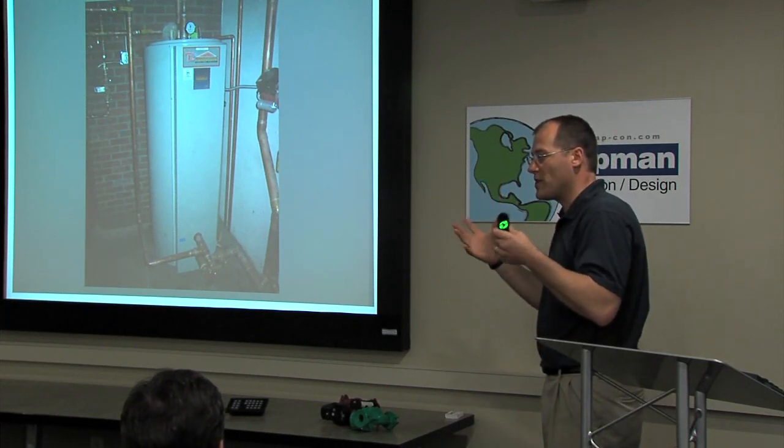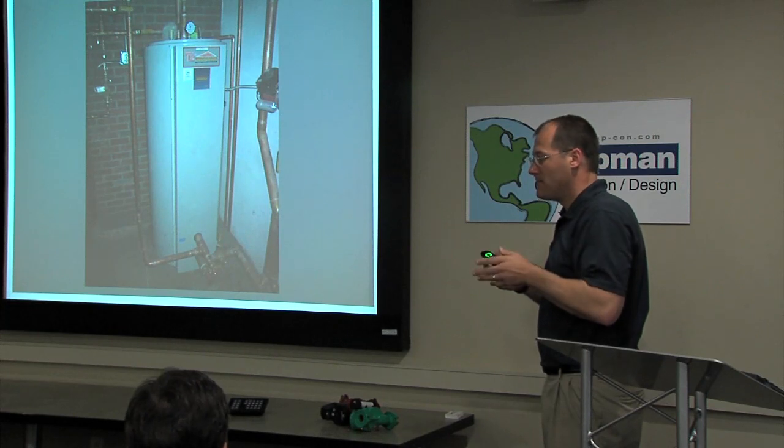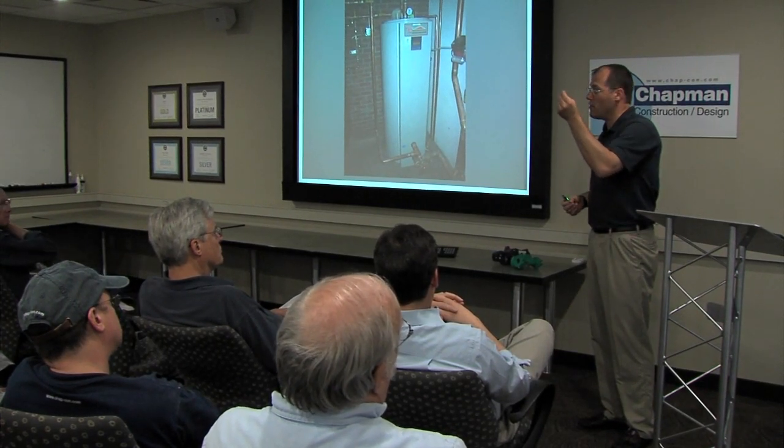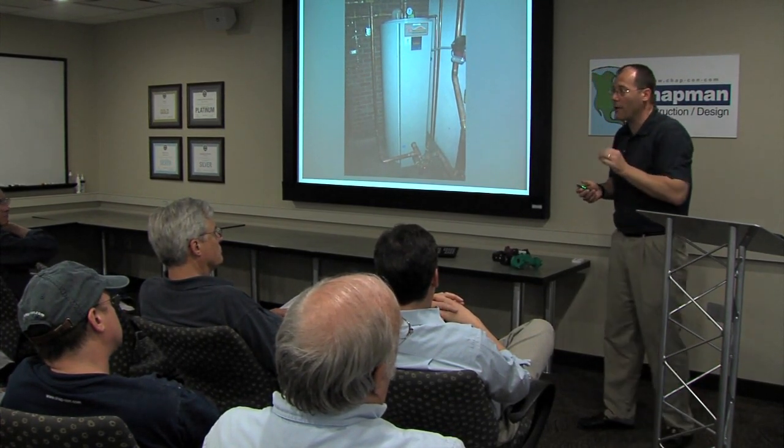As rules of thumb, we always think about 220,000 BTUs as about the most horsepower I can put into a 120 gallon tank of water. I just can't pump any more through that, and the surface area is not big. Flip that around and you can get about 900,000 BTUs of heat exchange if your vessel is full of boiler water and you've got a series of small copper coils carrying your domestic water. When there's no flow, you're storing almost no domestic water. When there's flow, it runs across the tank and can pick up about 100 degrees of temperature rise.